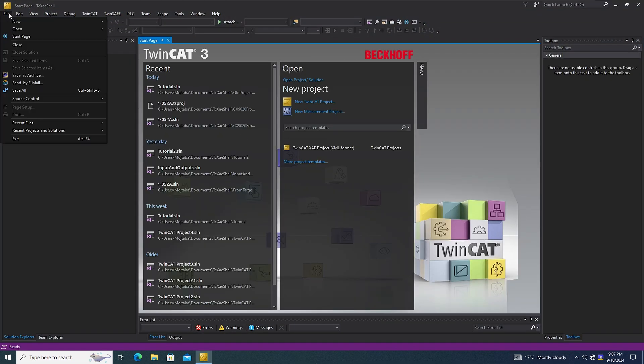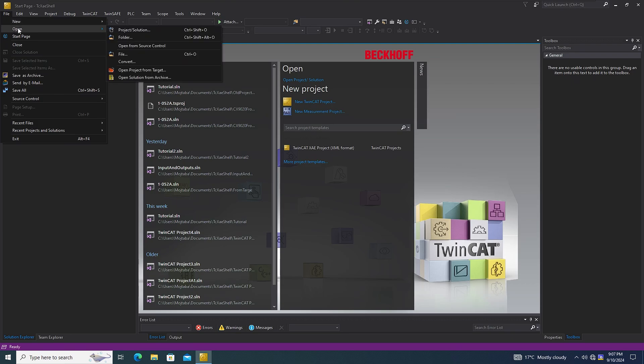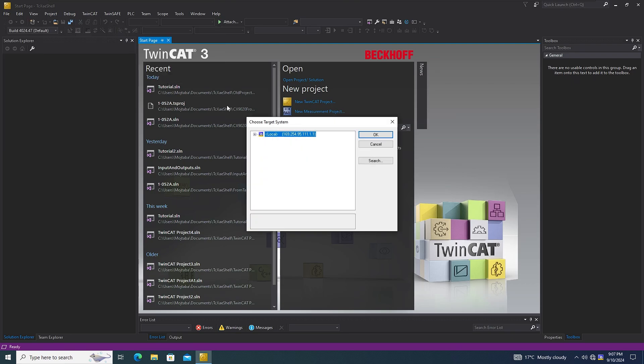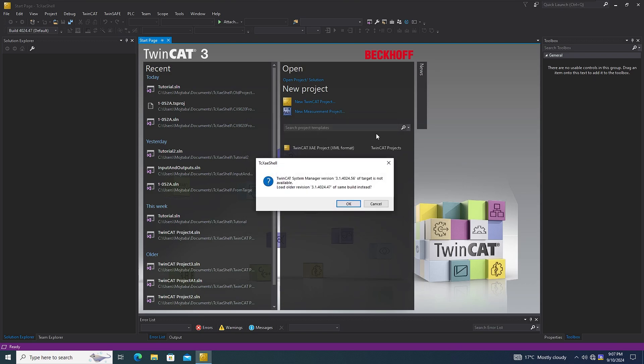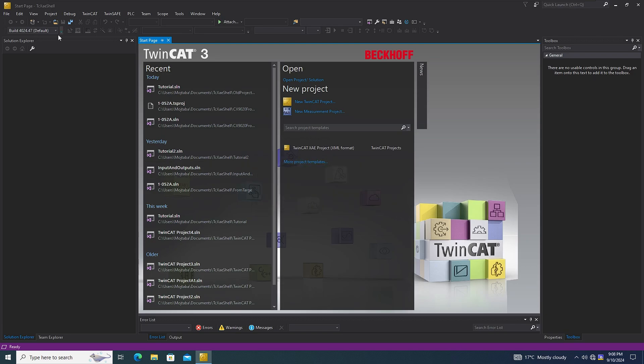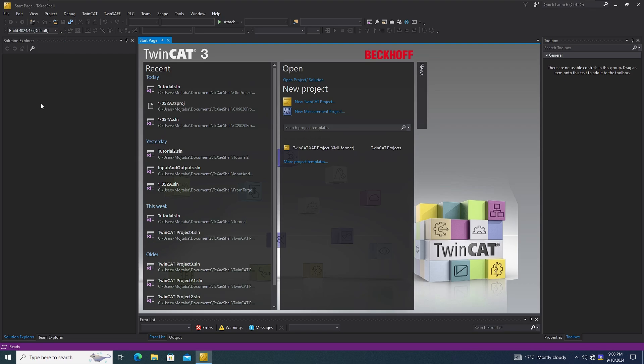Because this one has got connected, I go Open From Target. It's going to open the PLC program that was connected. If you pay attention it says 4024.56, so this is the version that the program for this PLC is written in. I have version 4024.47, so whatever this version is, you have to open the same version. When you install them all, you will see a listing here and you can choose the right version.